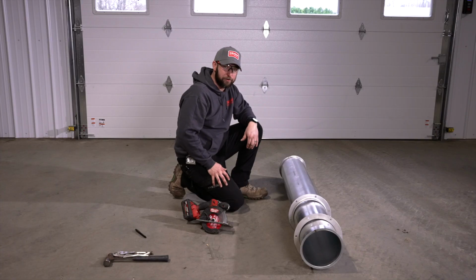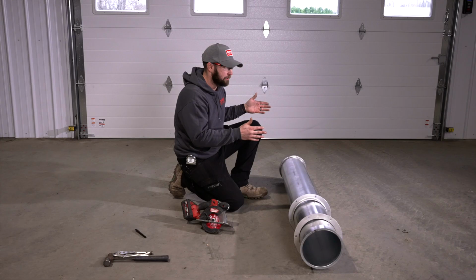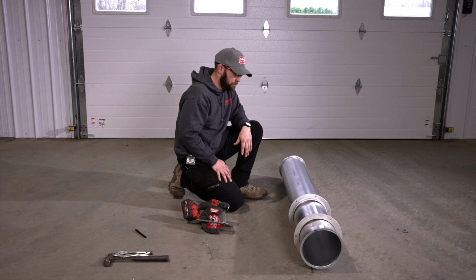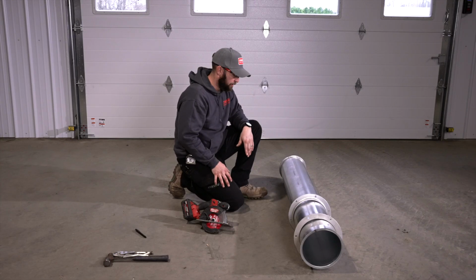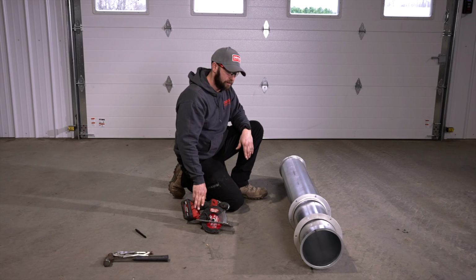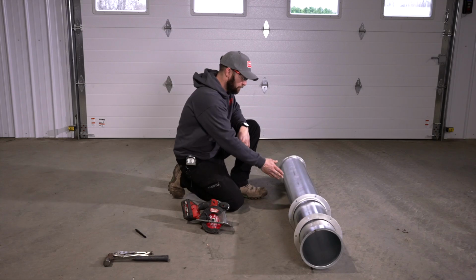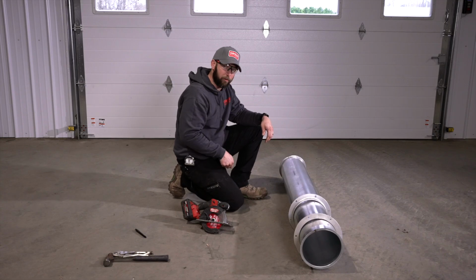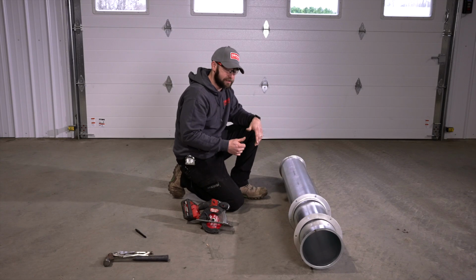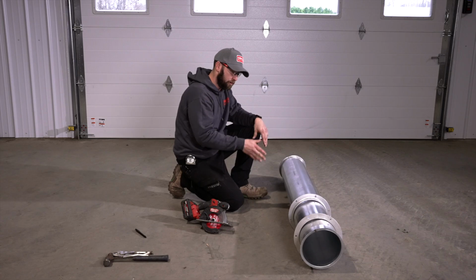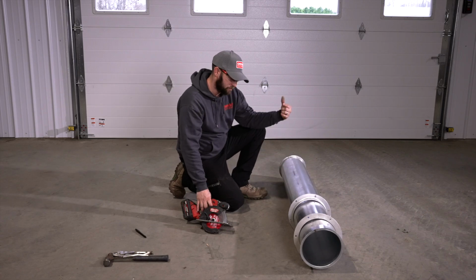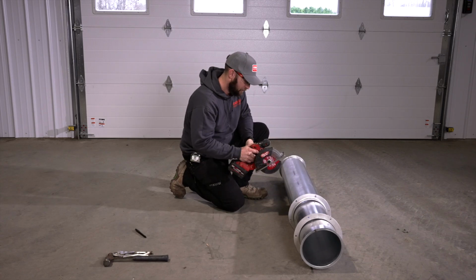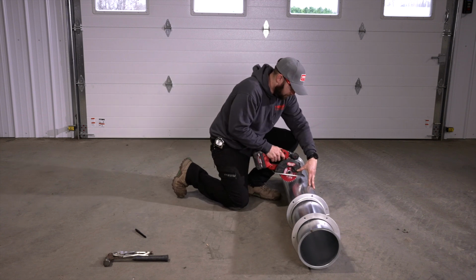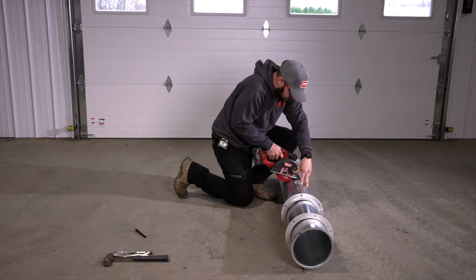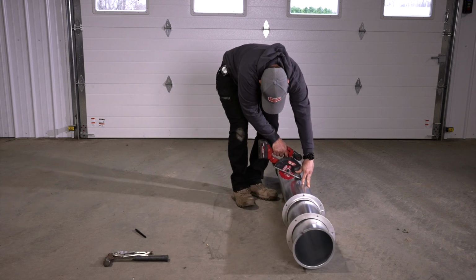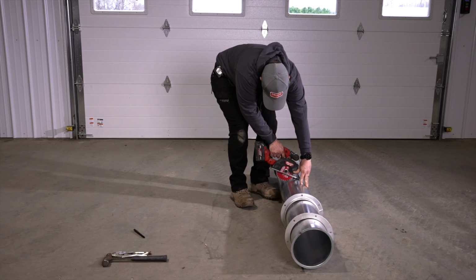All right, so before you start cutting, you want to make sure you're facing away from anything you want to protect or any people, because the saw likes to throw hot metal chips as you're cutting. And also when you start your cut, you want to start with your plunge cut on the weld seam, because the saw blade likes to kick when you go to cut through a weld seam. So you start it on the weld seam and then continue around the ductwork. So you're going to line your saw with your mark, line your circular saw blade up with your marks on the back and plunge that.